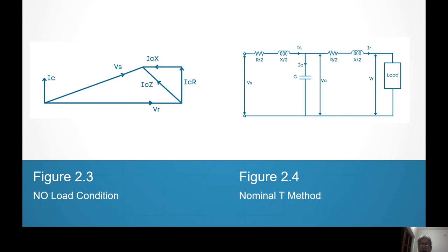And that can be removed by using shunt reactors and thyristorized controlled reactors. The thyristor is controlled by a processor, so that automatically the voltage VR is kept more or less equal to VS, and regulation is practically zero. That means very good regulation is achieved. That is what is done nowadays in the modern design.